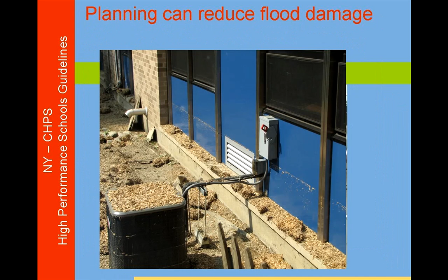So all of that dirty water poured right into every classroom in the building, right through the unit ventilator. Had this building been designed with a rooftop HVAC unit that had ducted supply and returns to each classroom, then although this still would have been a damaging flood, the water and the flood conditions would not have had direct access to every single classroom in the building.